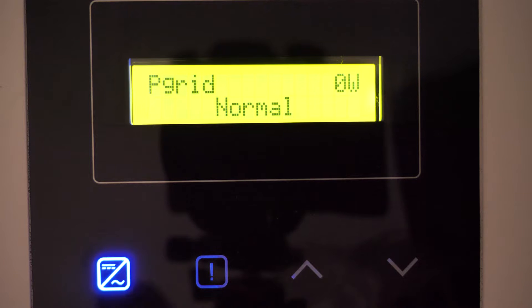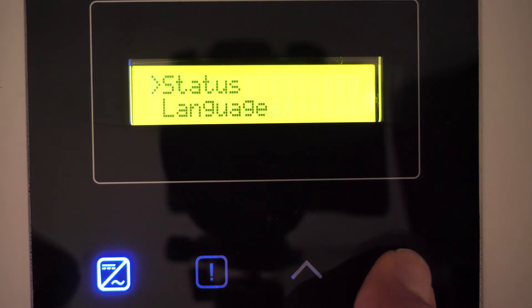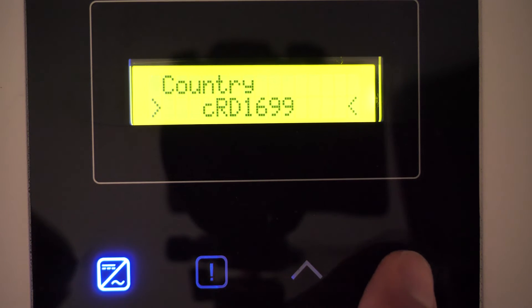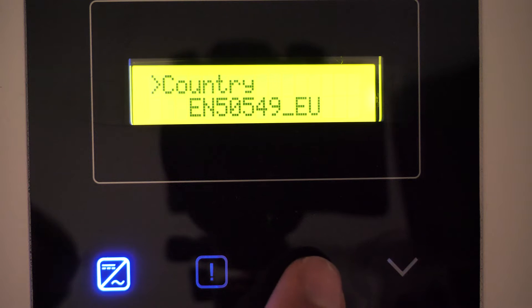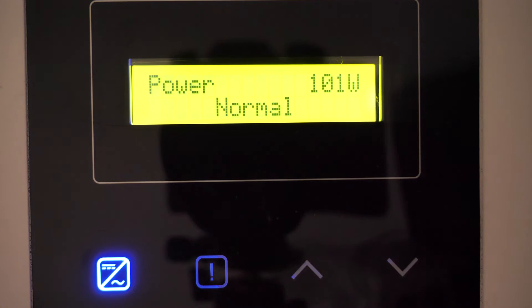It should be noted that on some Solax X1 models, especially the most recent ones, the zero injection system does not work correctly with the Spain grid code, so we need to change the grid code to a European one. To do this, go to Settings, enter the password 6868, go to Safety, and configure the network code to EN50549_EU. Press down to validate and exit. To verify, re-enter and you will see the European network code is memorized. With this grid code the zero injection will work correctly, as this is a minor firmware issue that will be corrected in future updates.